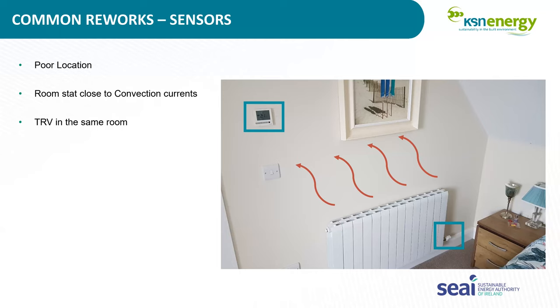It needs to give an indication of the overall temperature of the house. The second one is that I colored them in the kind of greeny colored squares. I don't know if you can see it from the image, but there's a thermostatic radiator valve and there's a stat. But putting two thermostats in the same room will cause a conflict. Whatever is set to the lower temperature is going to determine the heat that comes in that space.